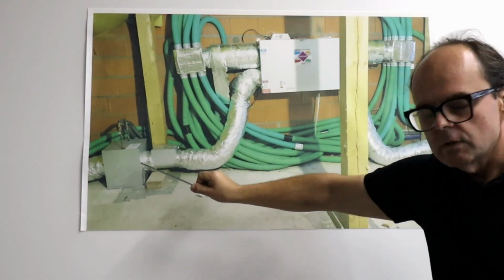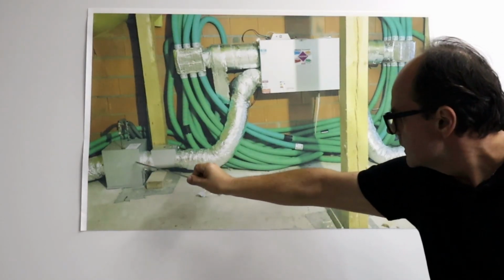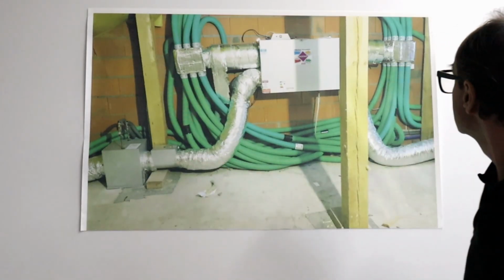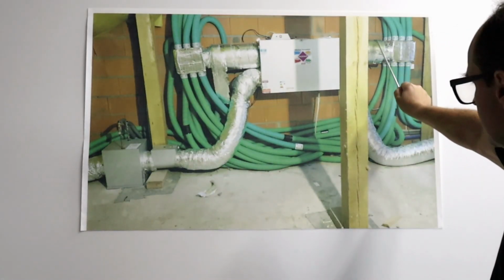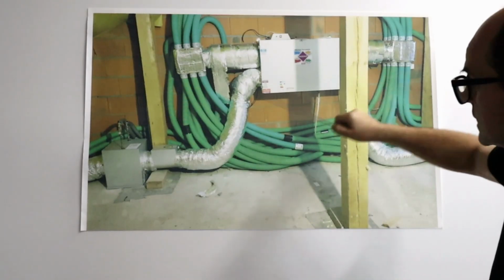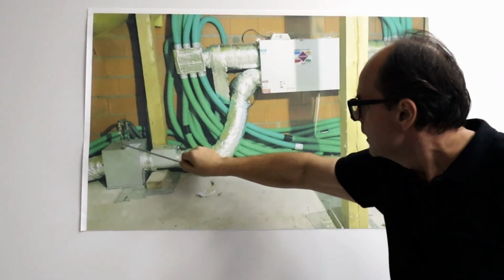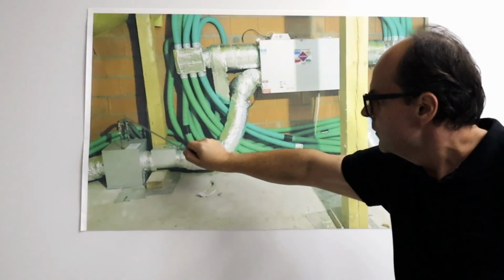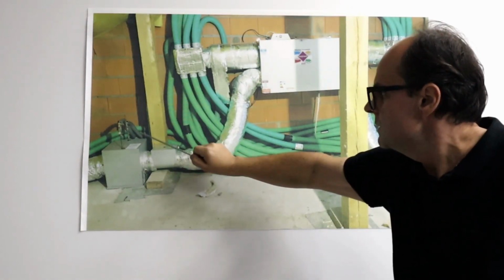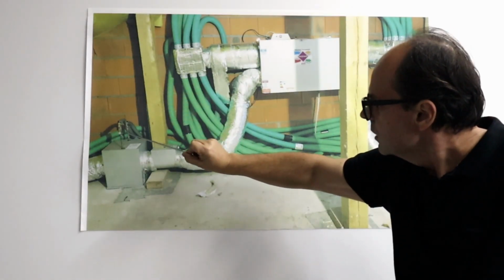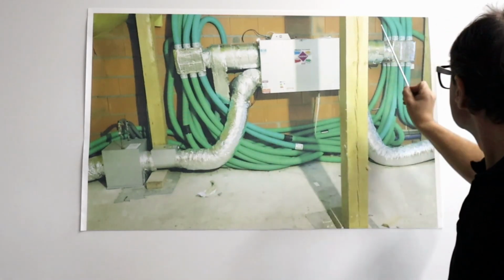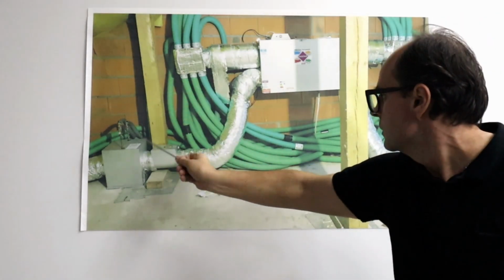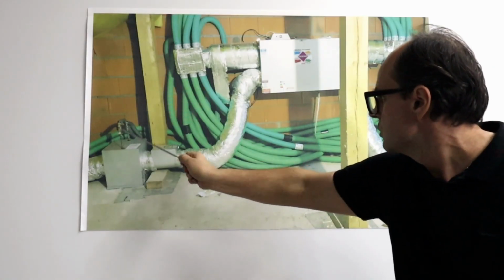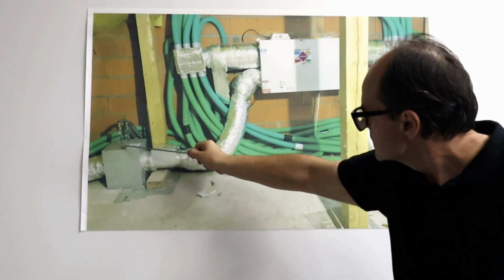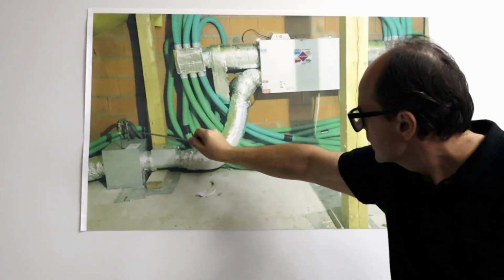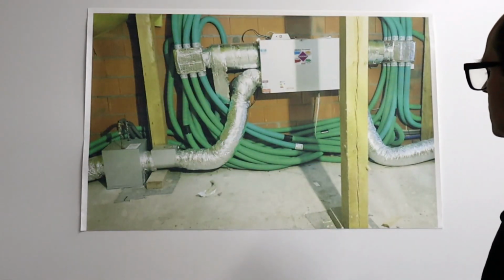A heater is quite different from a cooler as it lacks an outlet and is not insulated, and this was meant to be connected right here on the air intake. And this was meant to be connected to the heat pump. The chilled water buffer tank is behind the heat pump, meaning that's where the connection to the water buffer is. This should be here. An egregious error. It's completely wrong. This should have been done on a glycol heat exchanger, but we know it isn't. I'm not even going into details like the insulation of these pipes and so on.